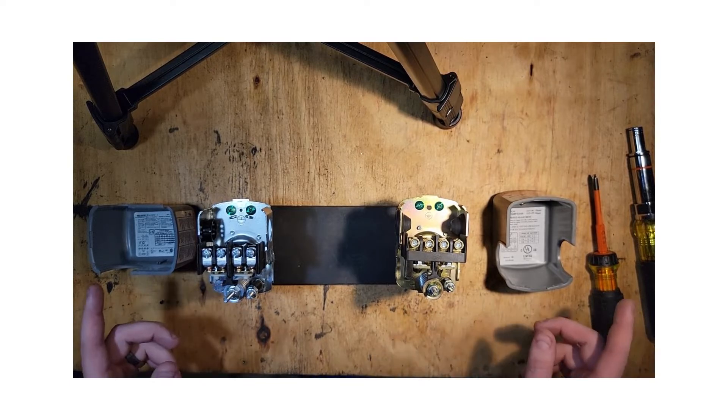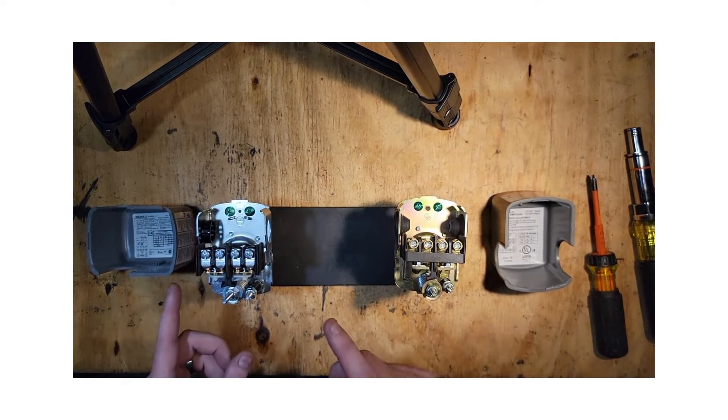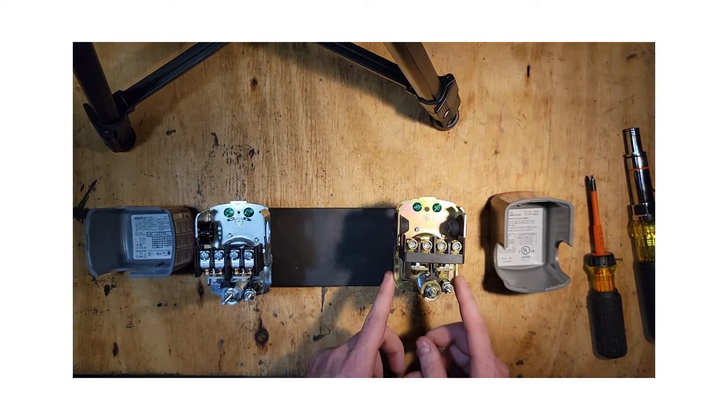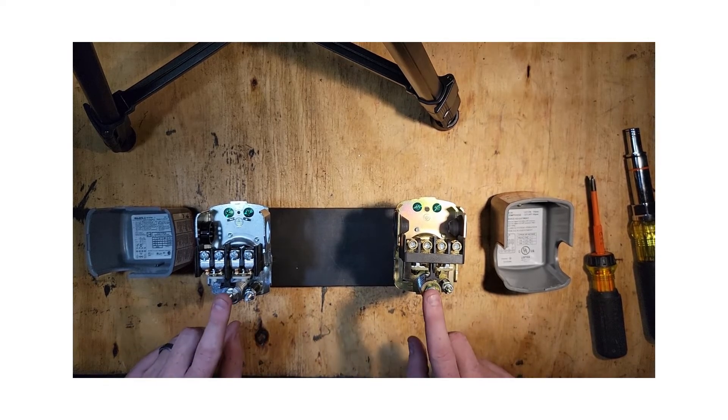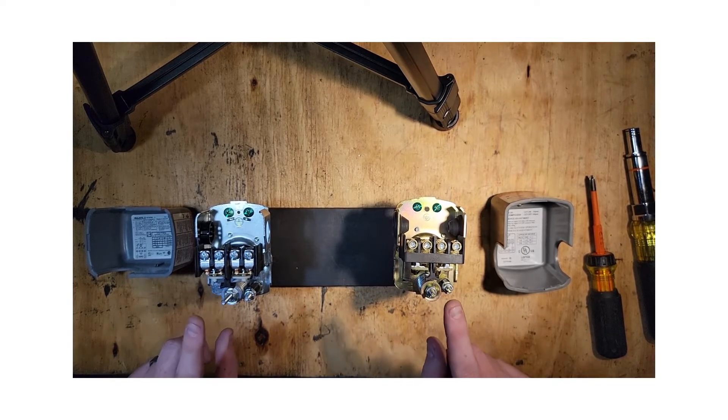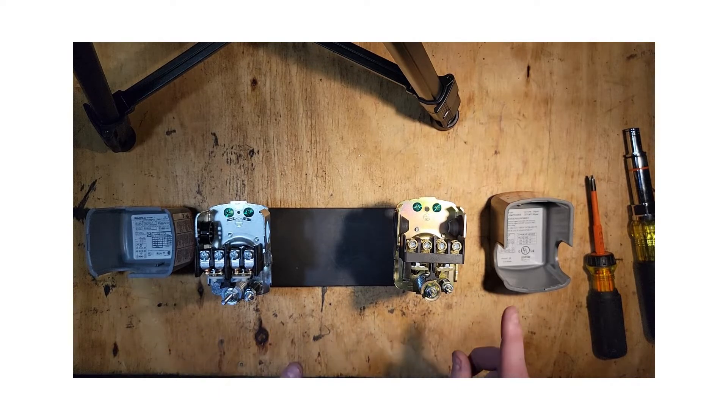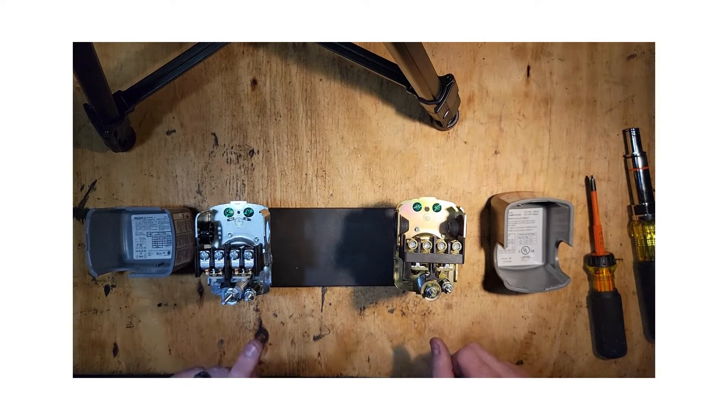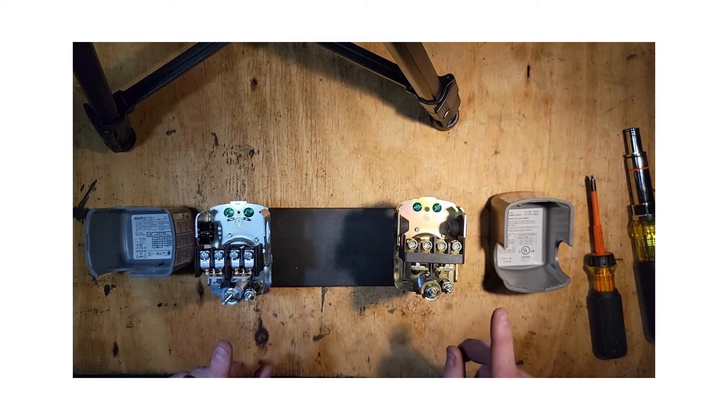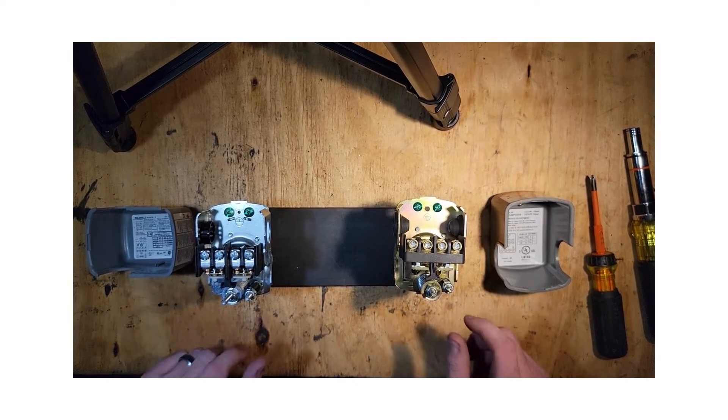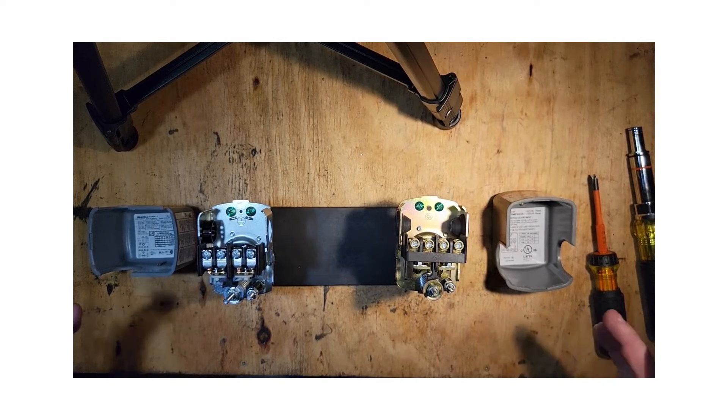So again, if you want to adjust the range from 40 to 60 or 30 to 50 equally, you adjust this. Tightening it increases, loosening it decreases. And if I want to only change my turn off pressure, I adjust this nut and again, tightening increases it and loosening it decreases it.